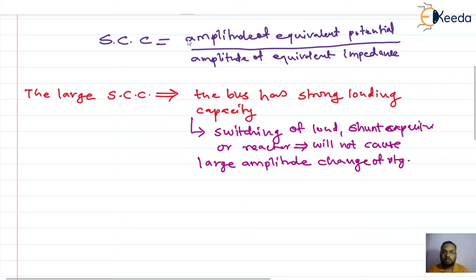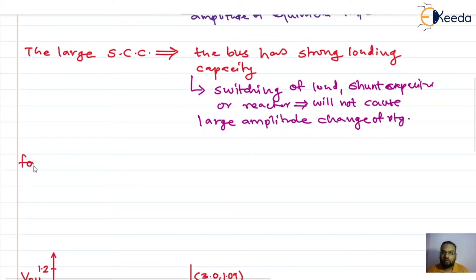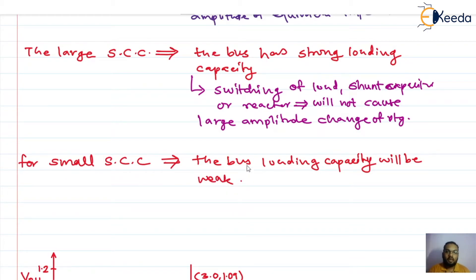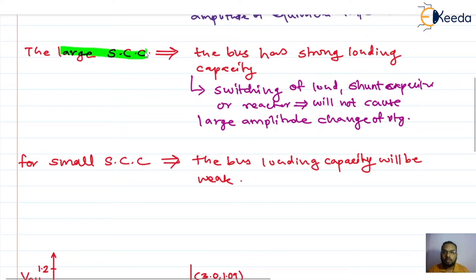On the other hand, for small short circuit capacity we will not have strong loading — the bus loading capacity will be weak. As the loading capacity is weak, switching of load, reactor, or capacitor will cause a large amplitude change in the voltage. So if we want better voltage stability, we go for a large short circuit capacity system, because switching will not cause any large change in the amplitude of the voltage.